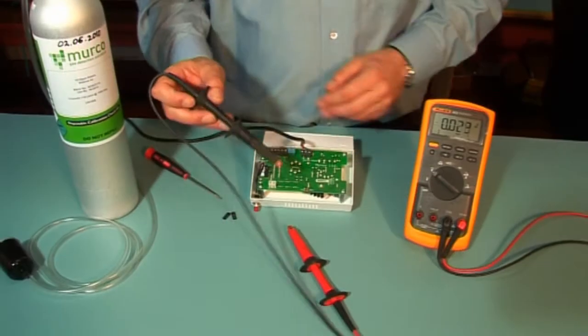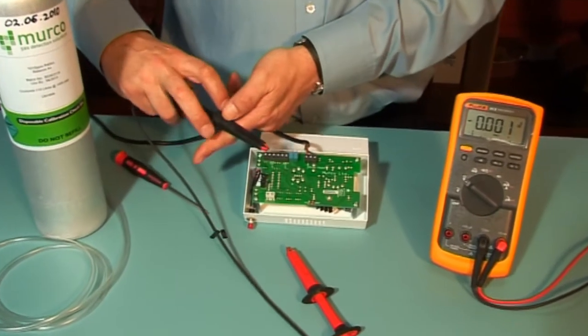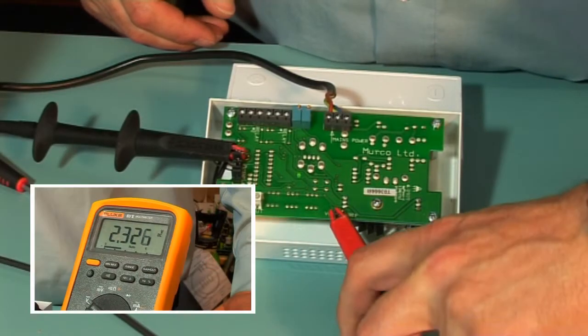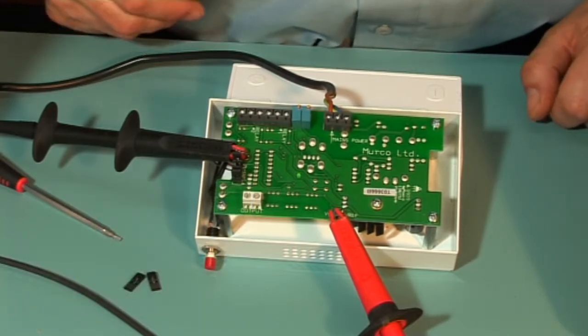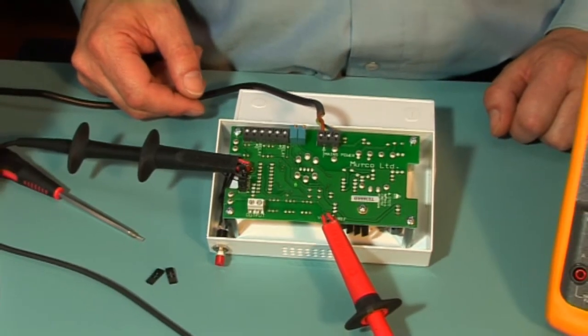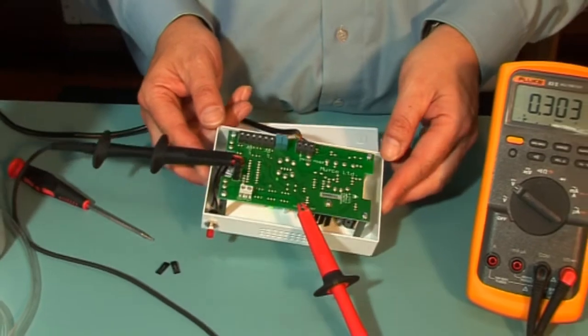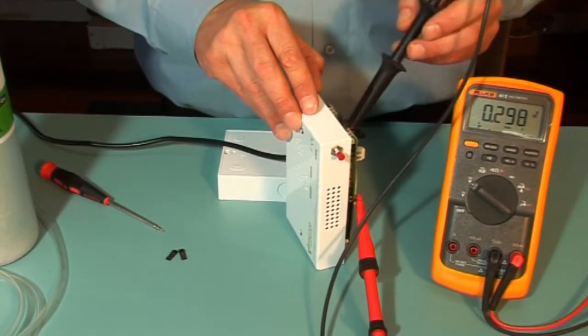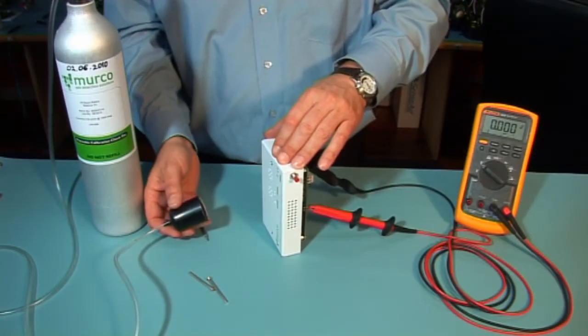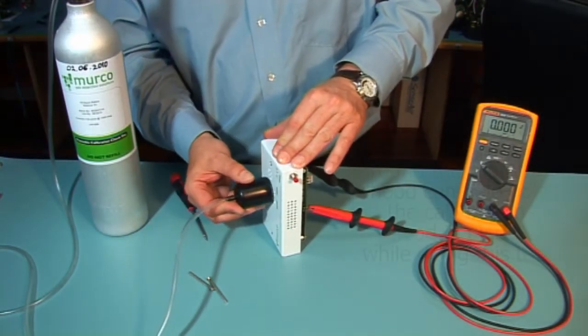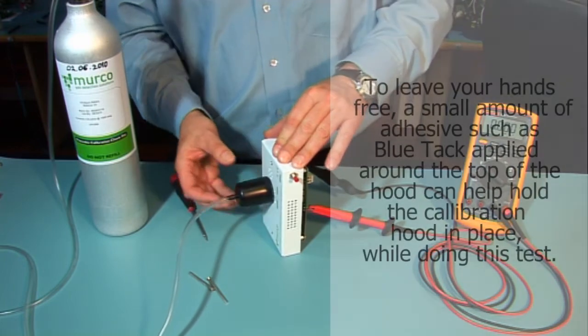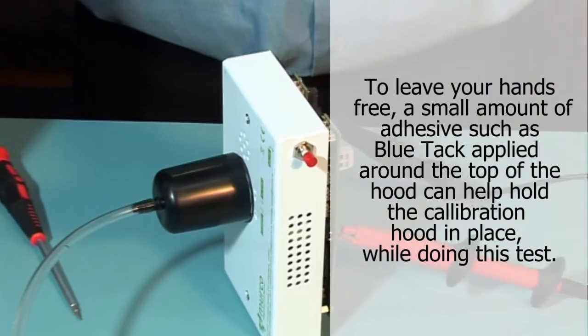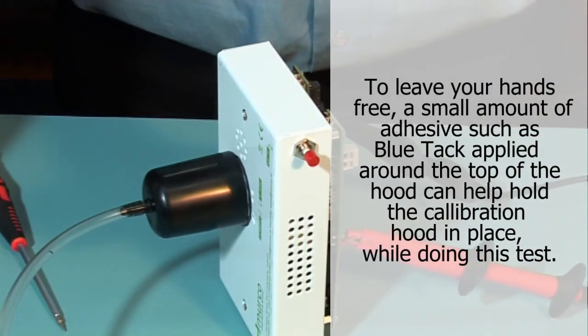Connect the voltmeter between V0 and Vs. Once the sensor starts to see gas, this voltage should increase. For a quantified test, you need to use a calibration cylinder for the target gas at the concentration as on the rating label or higher. Having carried out the electrical setup, expose the sensor by introducing gas through the front panel here. You should see the standby voltage increase. It may take 10 to 15 minutes to pass the alarm through this set point. Older sensors may take longer.